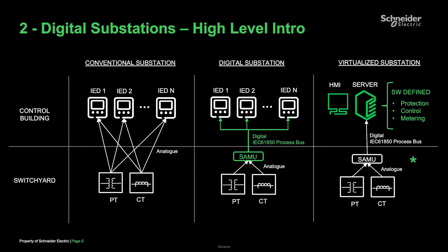And then finally, what we see the future looking like is a virtualized substation. In this case, you still have your merging unit. That merging unit might be, in the future or even today—some manufacturers are working on this—integrated with your PT and CTs, so you get digital signals directly. But instead of having all the separate individual IEDs, now you have software-defined functions or software-defined devices running on a server. So you'd have your protection functions, metering functions, and control all running on a centralized server. At that point, you don't have IEDs anymore—you have software running your substation. This is how we see the digital substation topic progressing.